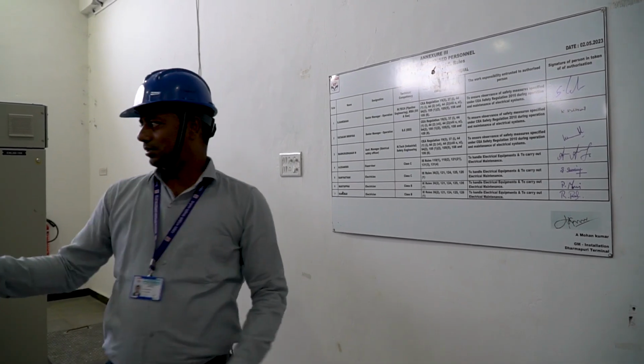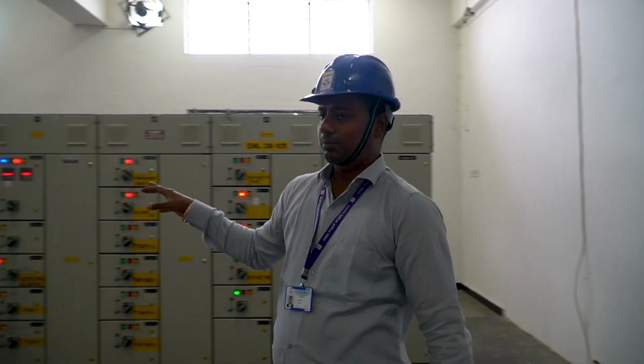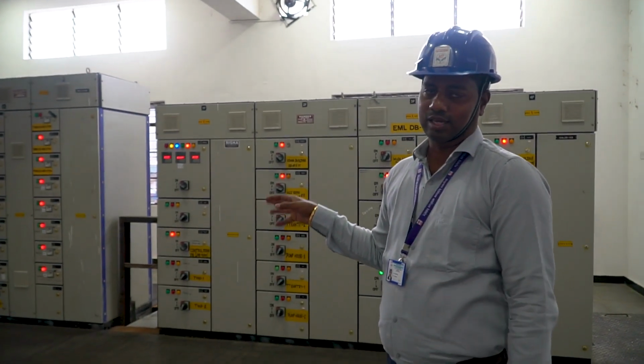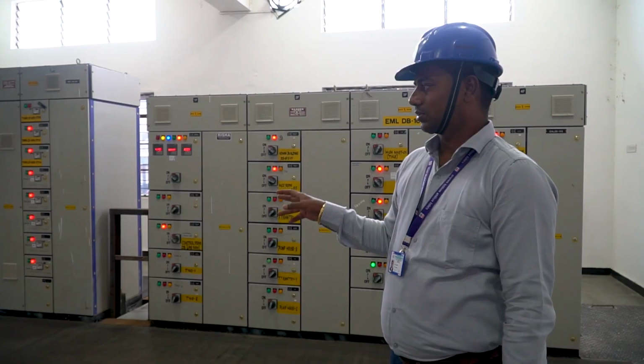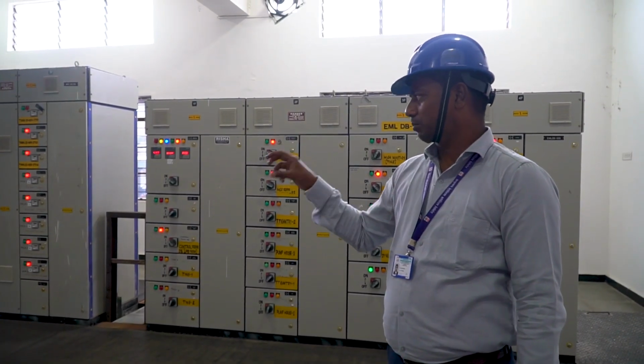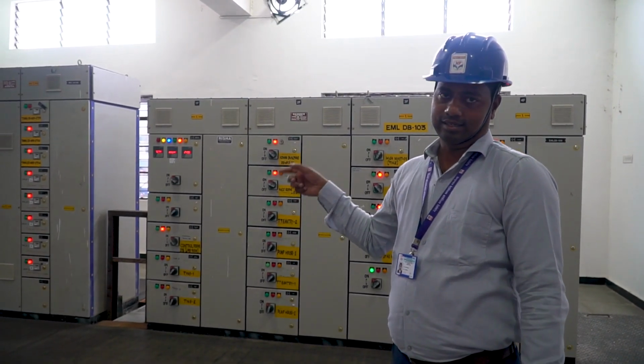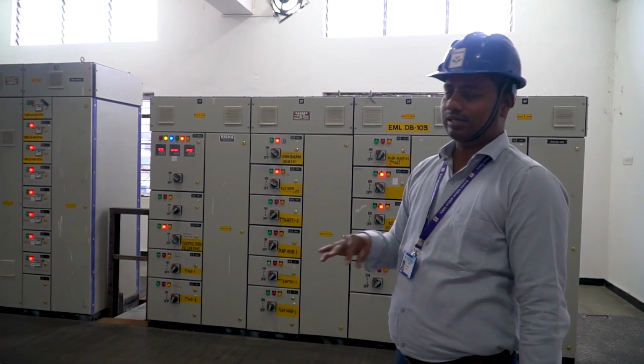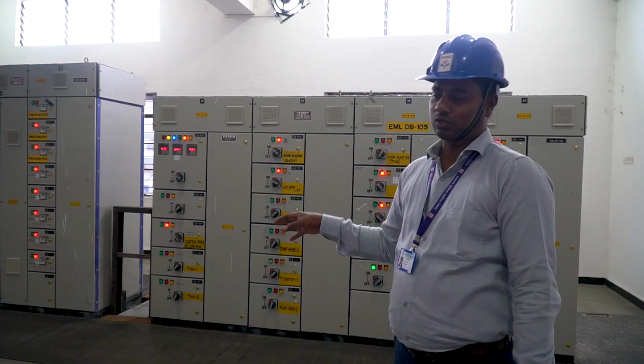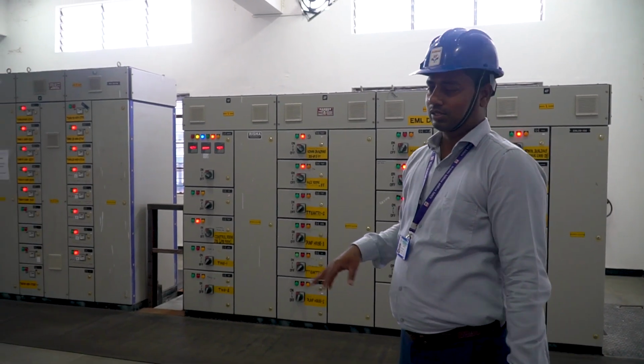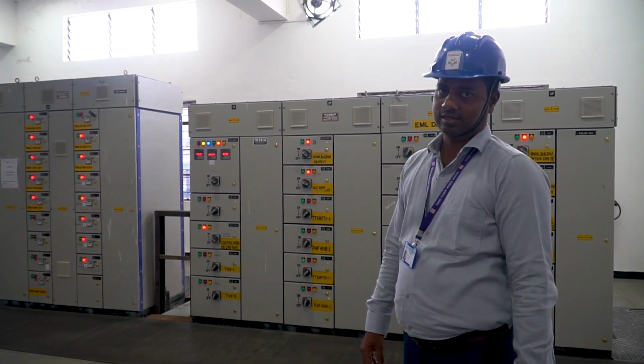Before we operate the panels, any panel has to be isolated. We have a concept called LOTO. When a panel is switched off, we put a tag, and from that tag the other electrician will know that the panel is under maintenance, so he will not touch the panel. That LOTO system is followed here. In case of a failure of a primary equipment, load can be shifted to the spare one and terminal operation can be continued.